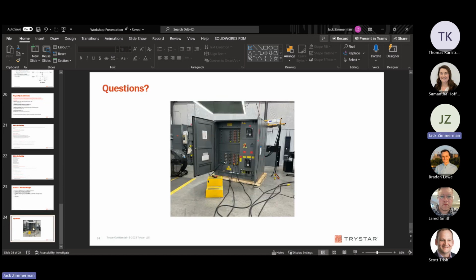So, for example, do we need to communicate on the unit a limited space and a restricted space? Yeah, confined space. So if you see here, this is a picture of it. It is flush full of stickers that say all sorts of different things, whatever we need for our UL 1008 listing, as well as the whole list that we have for our safety and standards. We just recently had the NFPA 70 training, correct? And in the examples I remember, they had a label on the piece of equipment that very clearly said restricted space and gave you a distance, and limited space to imply when you needed PPE and things like that, arc flash ranges. So since you're saying there's a condition under which it could still have voltage, do we need to label it to communicate that?